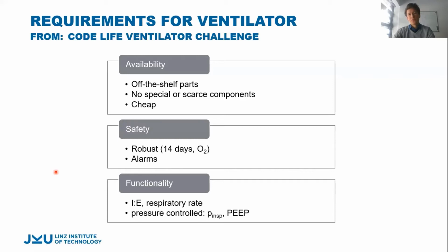And you can group these requirements into three subgroups. The availability issue, because this produced the problem that there are very special components that are not available on the market anymore if everyone buys ventilators. It should use off-the-shelf components. The safety issue: it should, of course, be robust. It should run at least for 14 days at 100% duty cycle. And it should also cope with an oxygen atmosphere, which is very corrosive. And the third one, of course, is the functionality: it is necessary that it works properly and that certain parameters can be adjusted.